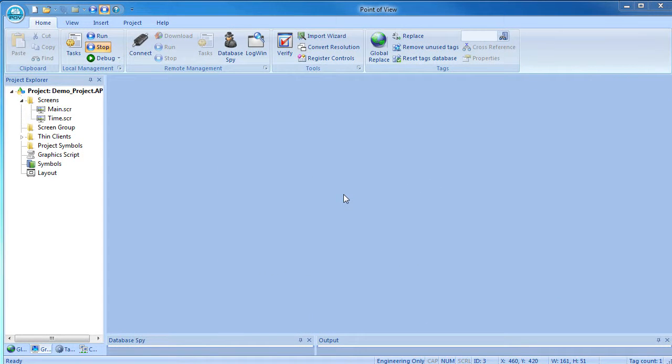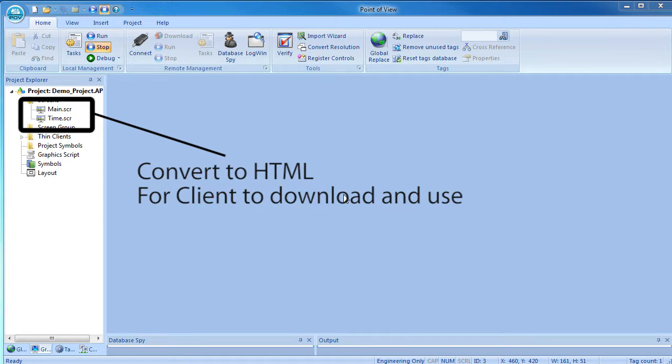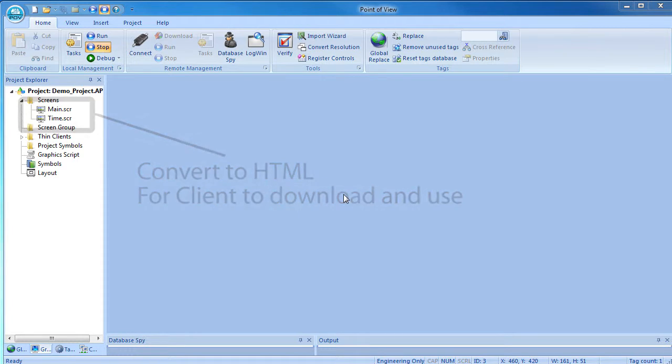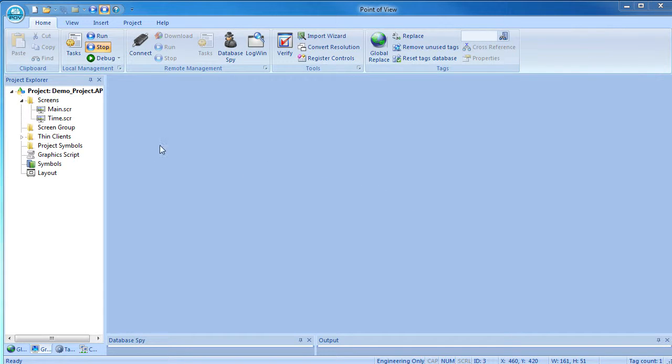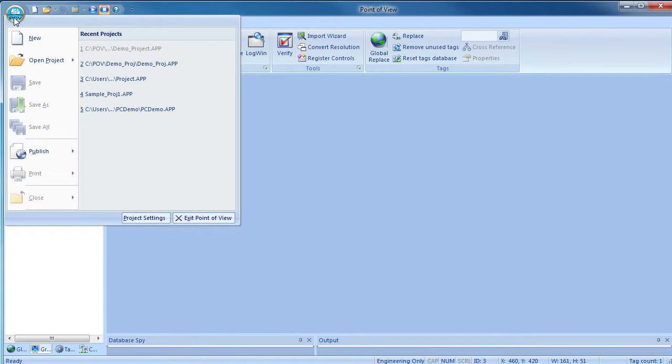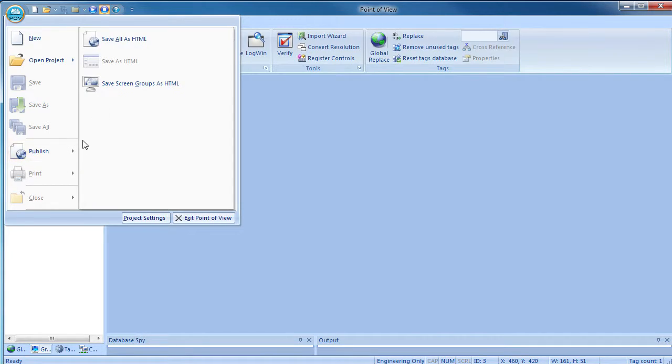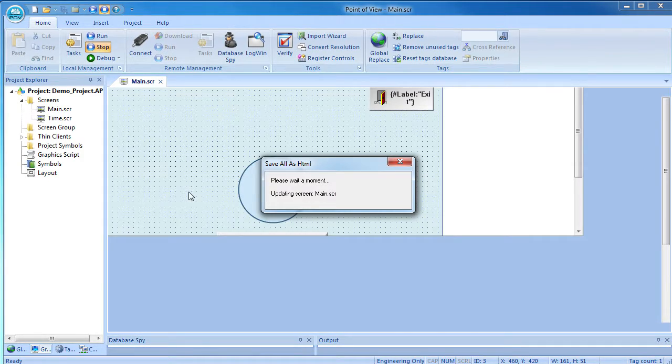The first thing we have to do is convert all of the screens we created down to HTML files that the remote client can download and use. There are a number of ways you can do that, but the easiest is to make sure all the screens are saved and closed and then click on the Point of View button and select save all as HTML. Easy.